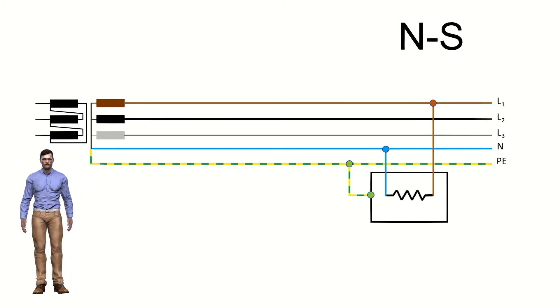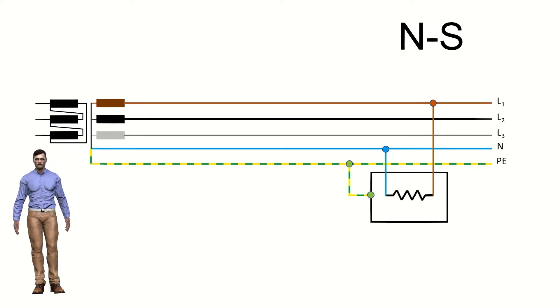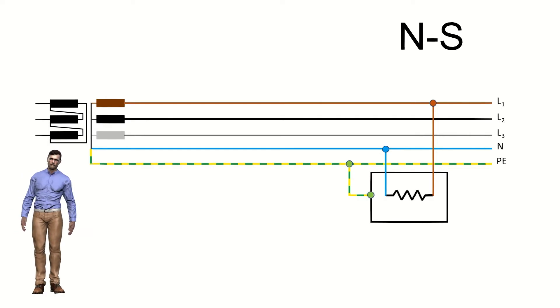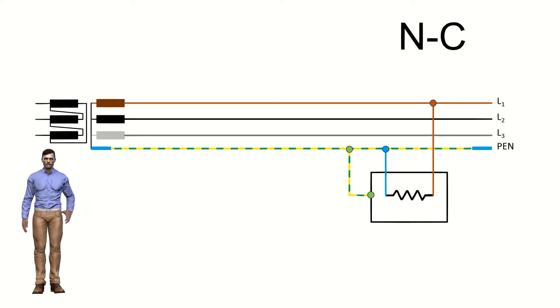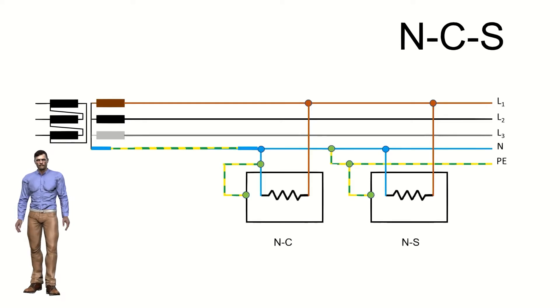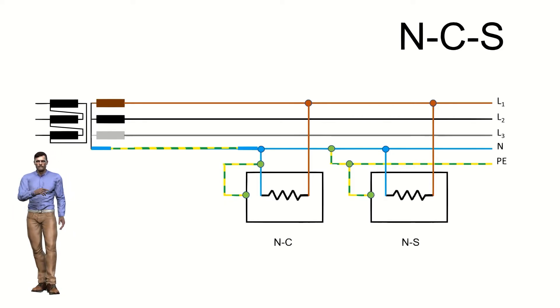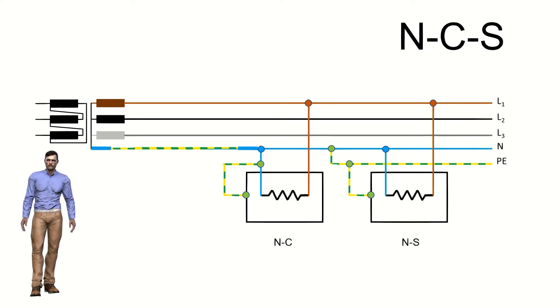Additionally, in this second case we can add a third letter that can take two values. The first option is the letter S, in which case two conductors arrive at the customer's loads: one the neutral and the other to connect the masses of the loads, which is called the protective earth PE. It is easy to remember this type of connection if we consider the letter S associated with separate lines. The second option would be the letter C, used to indicate that only one line is used that simultaneously acts as neutral and connects the masses — associated with a common line. We can also have electrical systems where both schemes coexist. So: S if they are separate lines, and C if it is only a common line.